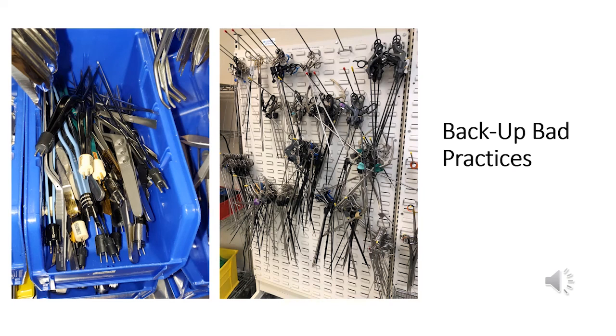Backup bad practices: in the picture on the left, there's just so much going on. Not only are there too many insulated bipolar or bayonet forceps, they also have mixed metal ones in there. The picture on the right shows an excessive amount of insulated laparoscopic instrumentation. If you need one that's in the back, you have to pull everything else, and other instruments scrape those shafts. So I would really advise looking at your inventory and trimming it down a bit, getting rid of instrumentation that's not being used, and maybe getting more of the ones that are being used.